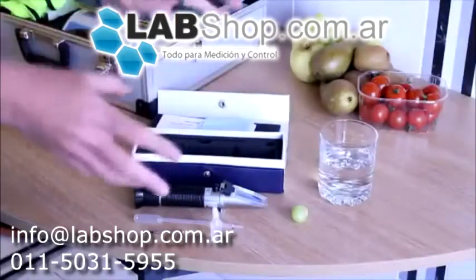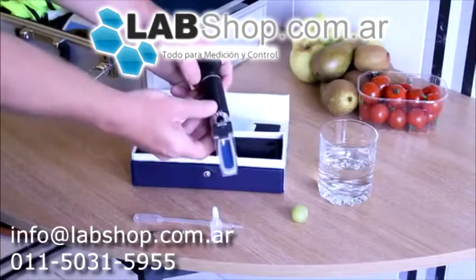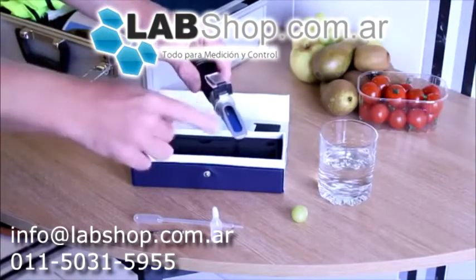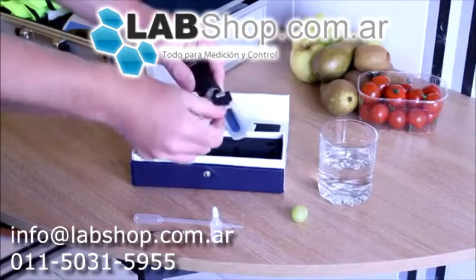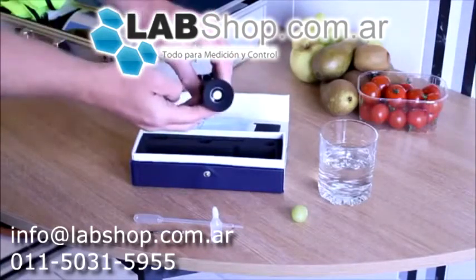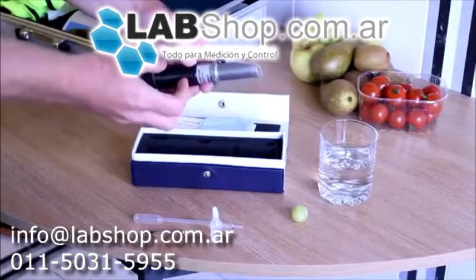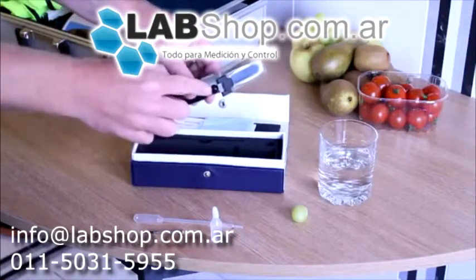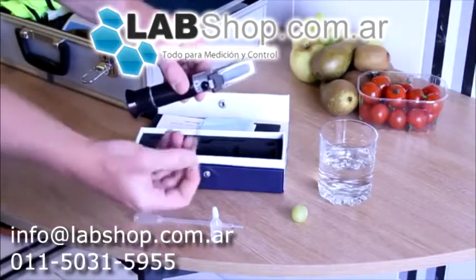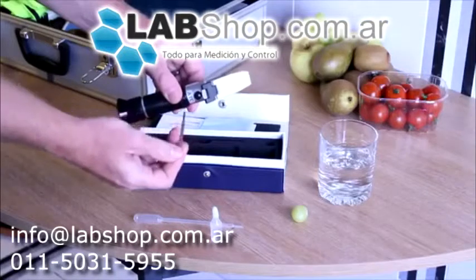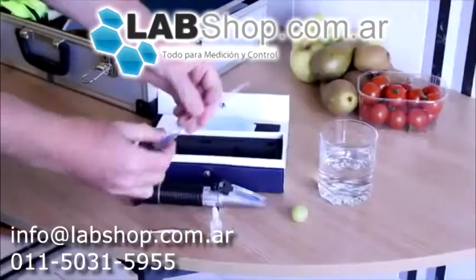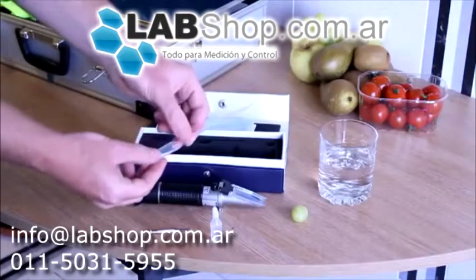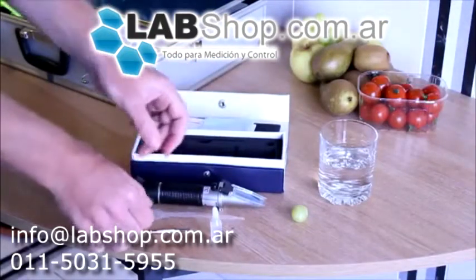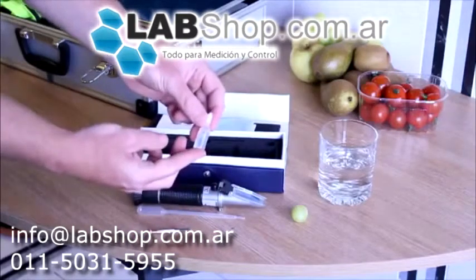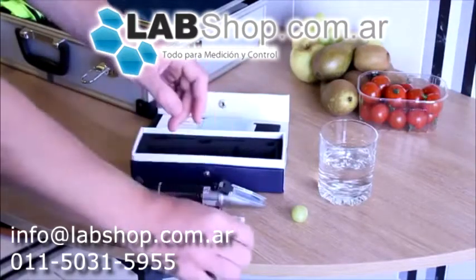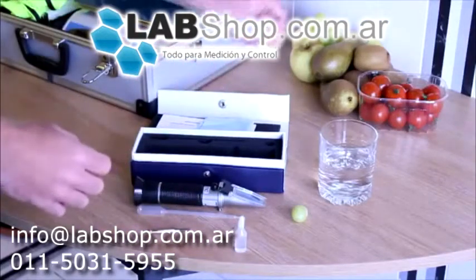So, let's take a look at how we actually use this device. You will see that the refractometer has a clear glass plate at the front with a clear plastic cover that folds over the plate, and then a viewing port on the reverse. Other features include a screw under this black cap which can be used for calibration, which is why you have the handy small screwdriver. The pipette will often be used for transferring liquid samples onto the glass plate. We use it particularly for transferring distilled water in terms of calibration.